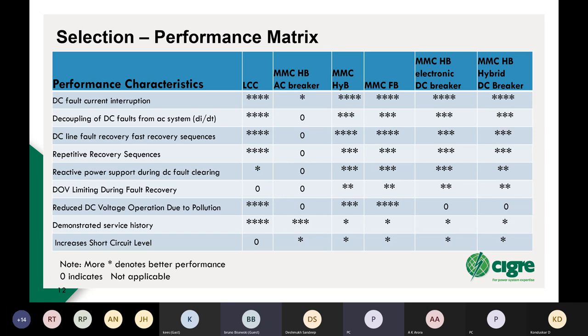As far as increasing short circuit level, LCC clearly doesn't provide any capability to increase the short circuit level, except perhaps if you consider that the delta transformers may increase line to ground short circuit levels, but that isn't any help in performance. All of the VSC technologies can deliver some increase in short circuit performance up to the load current of the DC system. So looking at the notes, you can see more stars denotes better performance. Zero indicates not applicable.